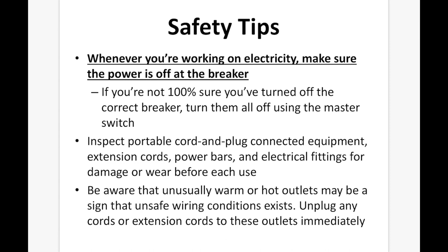You should always inspect portable cord and plug connected equipment, extension cords, power bars, and electrical fittings for damage or wear before each use. Be aware that unusual warm or hot outlets may be a sign unsafe wiring conditions exist. Unplug any cords or extension cords to these outlets immediately. Ensure GFCIs are installed in wet or damp areas, as the risk of electric shock is greater there.